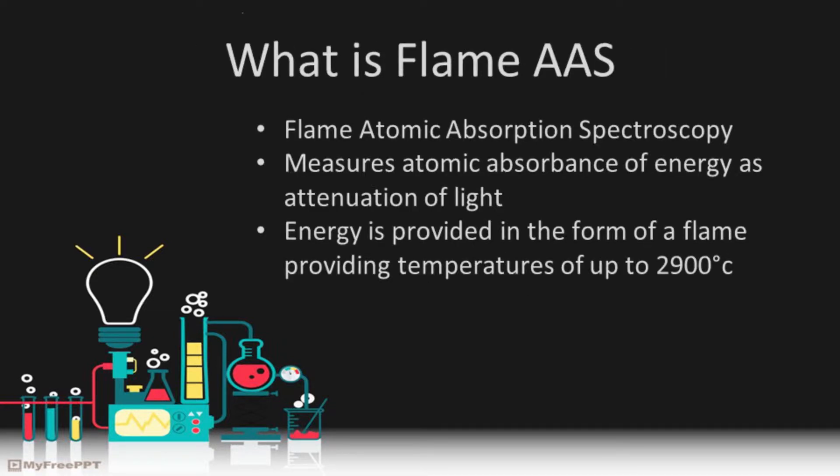Now we'll move on to the instruments used to analyze iron, starting with flame AAS. AAS stands for Atomic Absorption Spectroscopy, which refers to an instrument able to measure the amount of energy absorbed by atoms. The absorbances recorded are directly proportionate to the concentration of atoms within the optical path. The flame atomizes the sample and converts it to a gaseous state, usually using an air-acetylene flame at roughly 2300 degrees Celsius. When higher temperatures are required, such as for oxide-forming elements, temperatures of up to 2900 degrees Celsius can be reached using a nitrous oxide-acetylene flame.